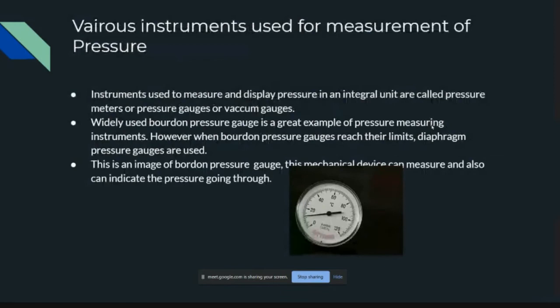Various instruments are used for measurement of pressure. Instruments used to measure and display pressure in an integral unit are called pressure meters, pressure gauges or vacuum gauges. The widely used Bourdon pressure gauge is a great example of pressure measuring instruments. However, when Bourdon pressure gauges reach their limit, diaphragm pressure gauges are used. This is an image of a Bourdon pressure gauge. This mechanical device can measure and also indicate the pressure going through.